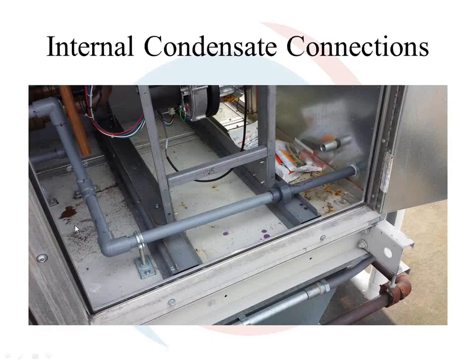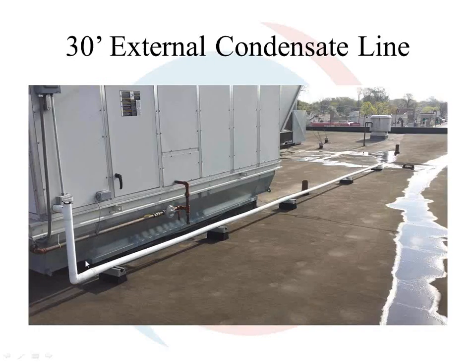This one didn't have a condensate neutralizer, but you can see the condensate line is going to the outside. Here's the condensate line, and the condensate line was probably 35 feet. Now it did have heat trace on it, but over 2 years, and the last winter, of course you all obviously know, was one of the most brutal winters we've ever had, that had no problems.